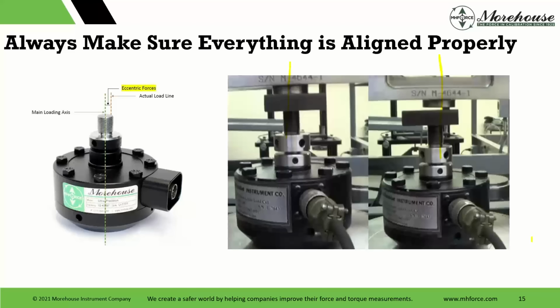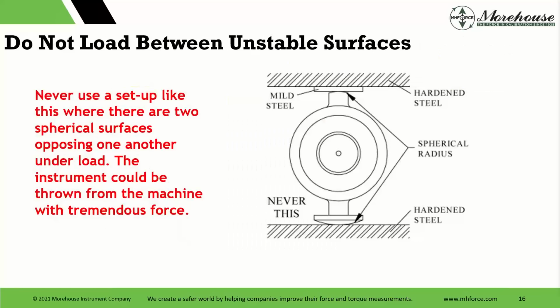So if I'm in a machine like a UCM, you can do this. Typically the bars will tip, but what you want to be aware of is if you have a ball-on-ball loading condition or other loading conditions and the technician doesn't align everything, things can kick. And if things kick, things can fly. So that gets us into one of the do not load between unstable surfaces.